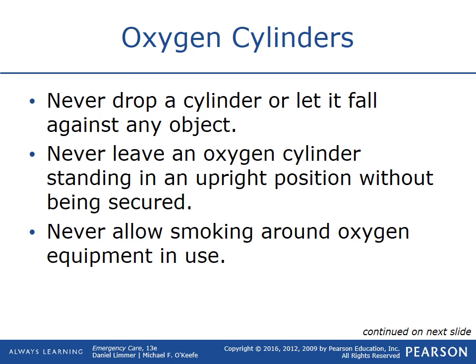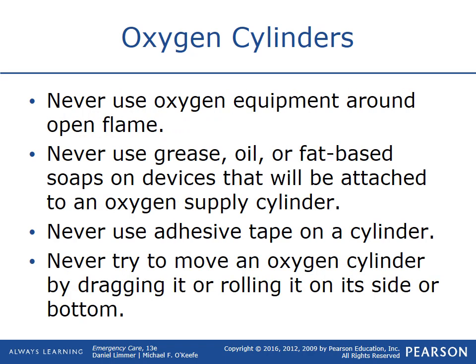Never drop a cylinder or let it fall against any object. Never leave an oxygen cylinder standing in the upright position without being secured. And never allow smoking around oxygen equipment in use. Never use oxygen equipment around an open flame. Never use grease, oil, or fat-based soaps on devices that will be attached to an oxygen supply cylinder. Never use adhesive tape on a cylinder. And never try to move an oxygen cylinder by dragging it or rolling it on its side or bottom.